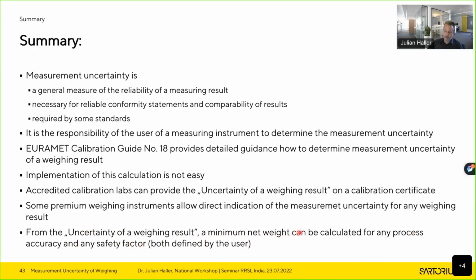The rationale between these two considerations is the same, but for small loads, you get a big relative uncertainty. But as seen, if you use the minimum net weight according to Euramet CG18, the first difference is there's a sophisticated uncertainty calculation behind all that, and the user can define process accuracy and safety factor matching his processes and applications. So that is a big difference to the USP minimum net weight. It has the same name, but it's not the same value.